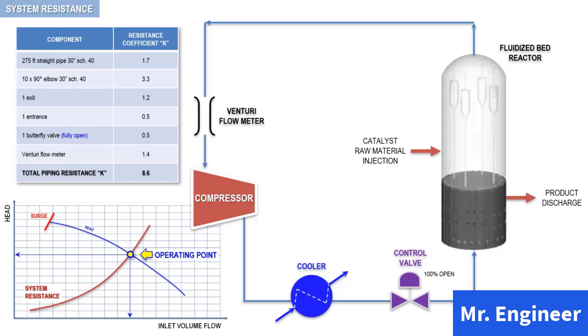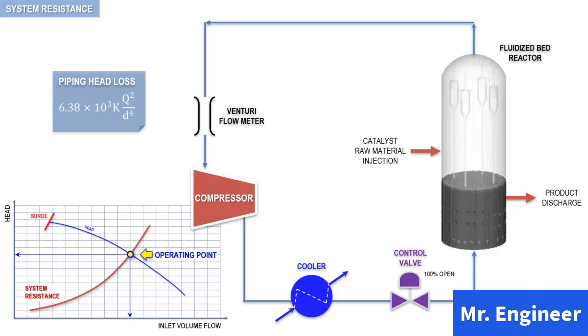This coefficient will be used in the head loss formula, as seen here. In this formula, K is the resistance coefficient, which is dependent on the control valve opening. It increases with reduced valve opening, resulting in increased head loss and system resistance.